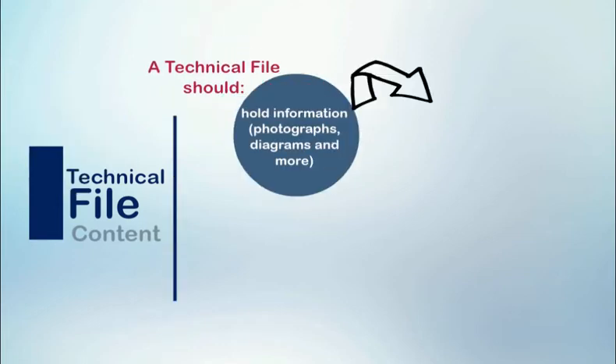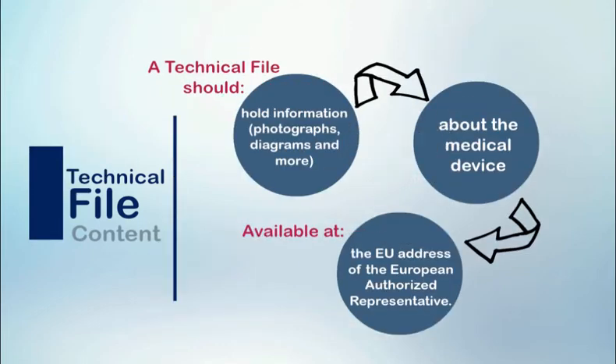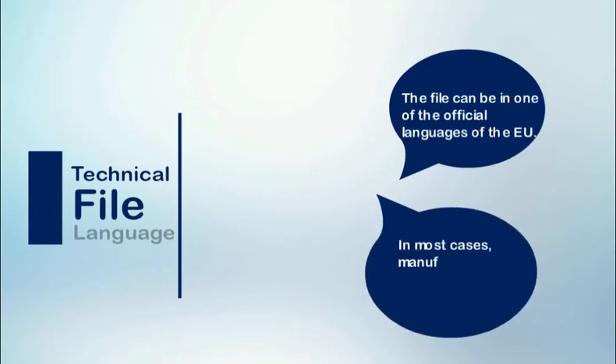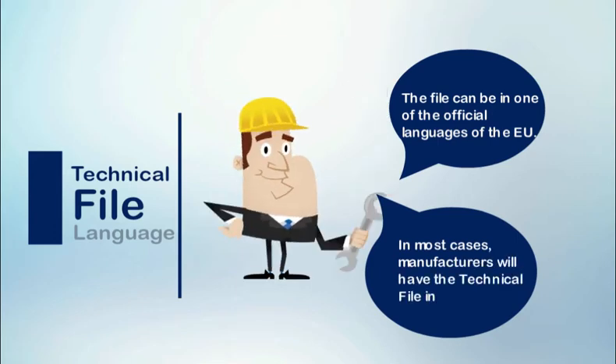A technical file should hold information such as photographs, diagrams, and more, presenting the medical device — to be made available at the EU address of the manufacturer or his European authorized representative. The file can be in any of the official languages of the EU; however, in most cases, manufacturers will have the technical file in English.